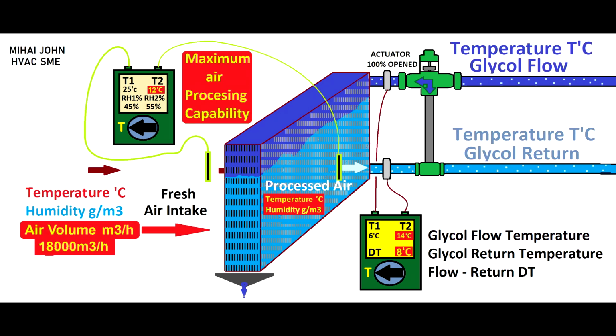The glycol temperature differential between the flow and return can be influenced by the increased air volume passing through the heat exchanger. In certain instances, driven by financial constraints and the desire to enhance production, some systems are subject to incorrect modification and are left inadequately conditioned. This scenario is visually evident in the provided image, where the air volume surpasses the air handling unit processing capacity. Consequently, the air remains uncooled, failing to attain the desired set point temperature. This leads to an escalation in the glycol temperature differential.